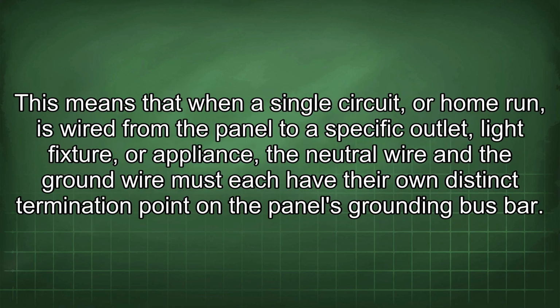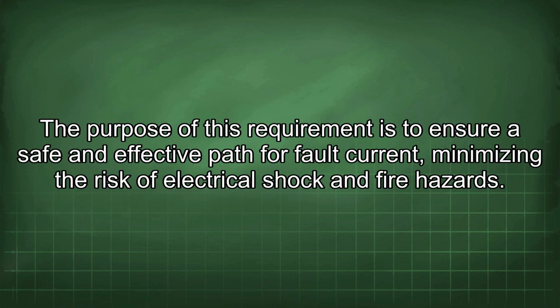This means that when a single circuit or home run is wired from the panel to a specific outlet, light fixture, or appliance, the neutral wire and the ground wire must each have their own distinct termination point on the panel's grounding bus bar. The purpose of this requirement is to ensure a safe and effective path for fault current, minimizing the risk of electrical shock and fire hazards.